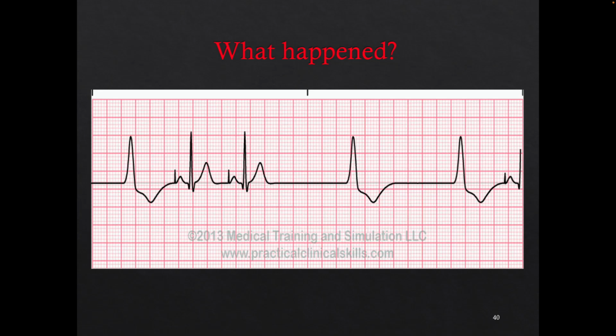This gets a little tricky. Is it loss of capture there, or is that just? Mm-mm. So loss of capture, you're going to probably see some kind of output, and there's no actual capture. So there's no ventricular response. It does. So now it likely oversensed in this. It thought it saw something and then didn't deliver an output, right? So that's when you want to adjust the sensitivity and you want to make it less sensitive, right? Because it thinks it's seeing something that it's not.